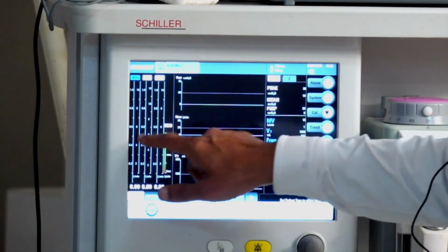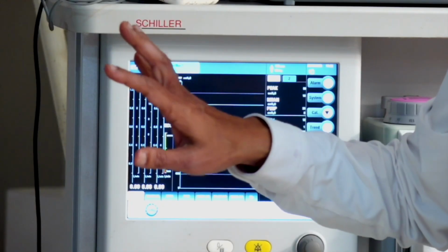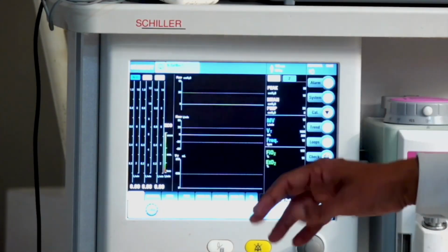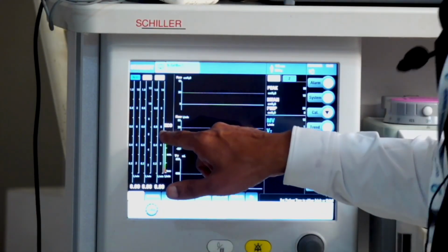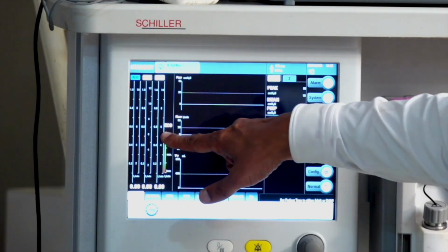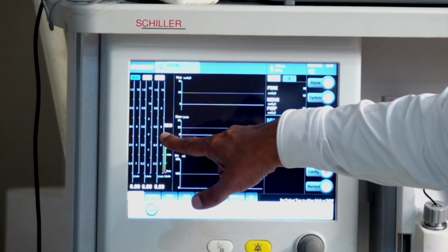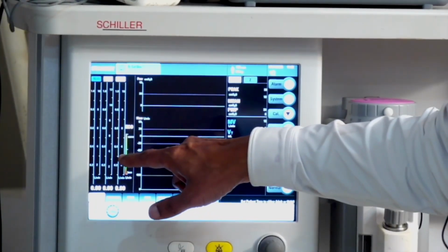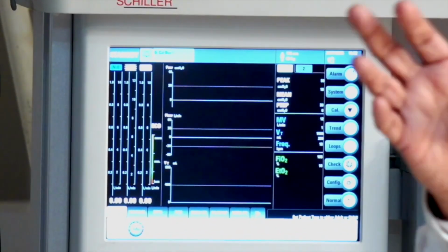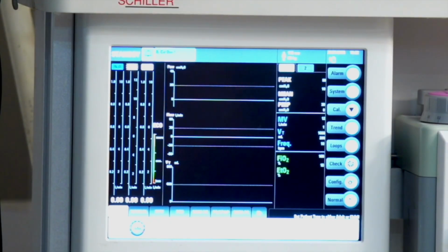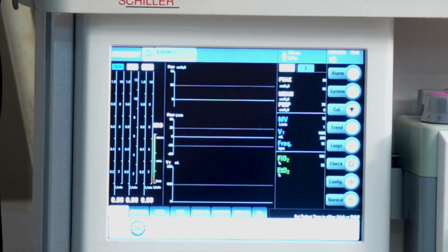This is called an econometer. Now, this tells you about the efficiency of your low flow anesthesia. If you give very high flow, it will remain in the upper part, okay, this part. So you know that you are not very efficient. When you reduce your flow and it is efficiently used, it will come into this particular zone. So it gives you a visual guide whether you are efficiently using low flow anesthesia or not. This is an additional tool, basically software, which is available in most of the advanced anesthesia machines now, in one form or other, and tells you that your low flow anesthesia is okay.